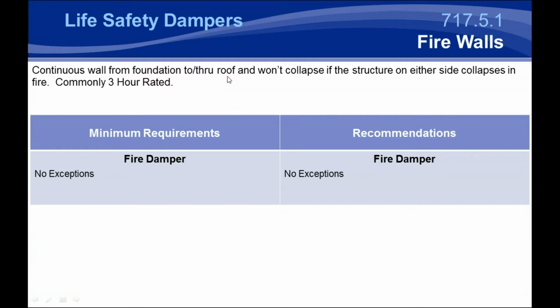So imagine a firewall separating a building between a left and a right side. If there's a fire on that left side, that firewall will stay throughout the fire and make sure there's no penetration and no fire going through that barrier, even if that entire right side of the building collapses. Because of that, the minimum recommendation and the minimum requirement is a fire damper. There's no exception to penetrations through a firewall.